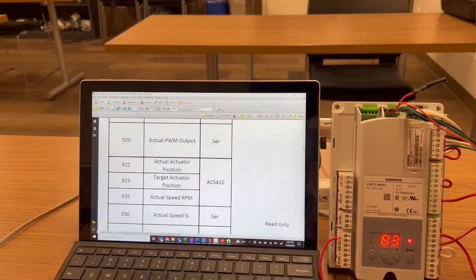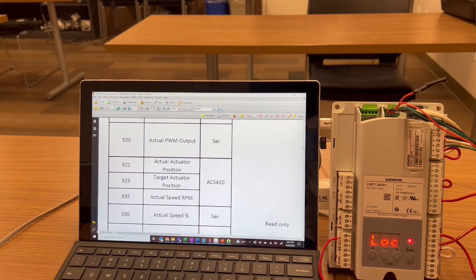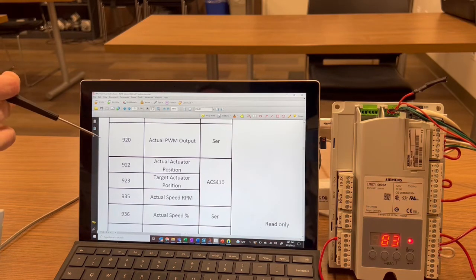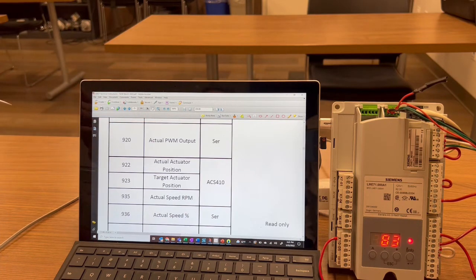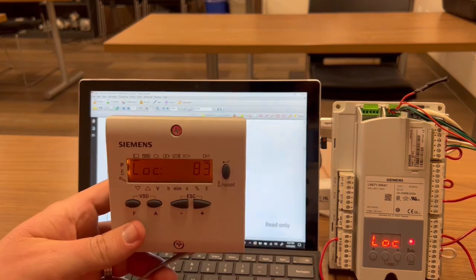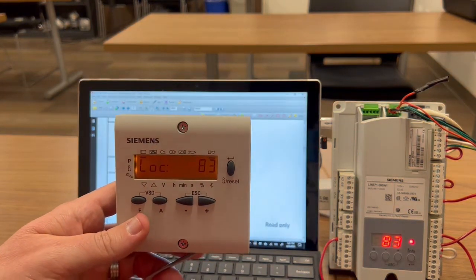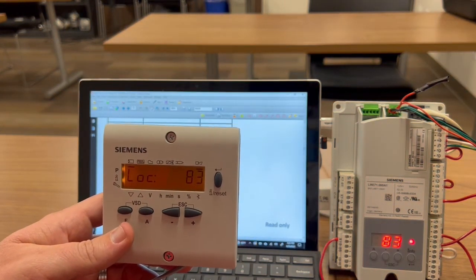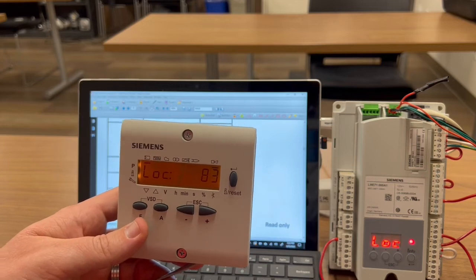Some helpful parameters for troubleshooting a lock 83 are parameter 920 for the actual PWM output and parameter 936 for the actual speed percentage. And you can access these parameters with a remote display. And you'll need to get into service mode to access these parameters.